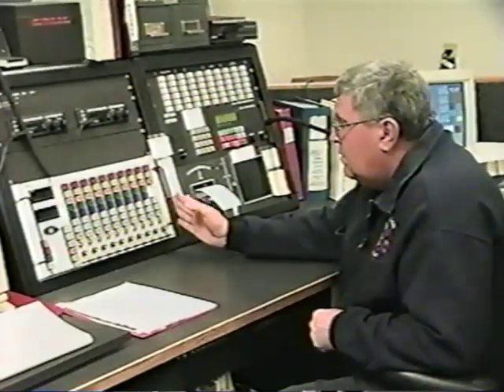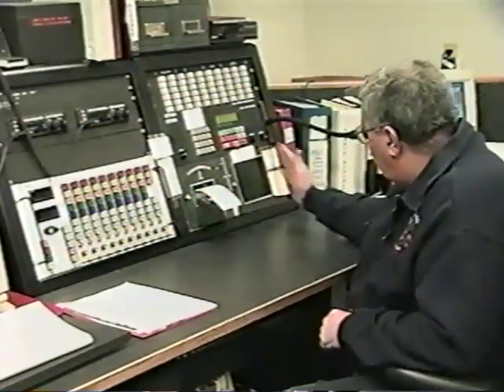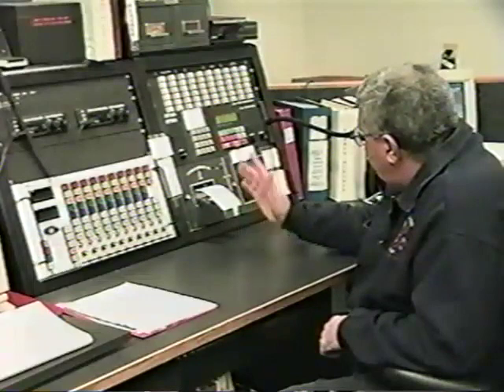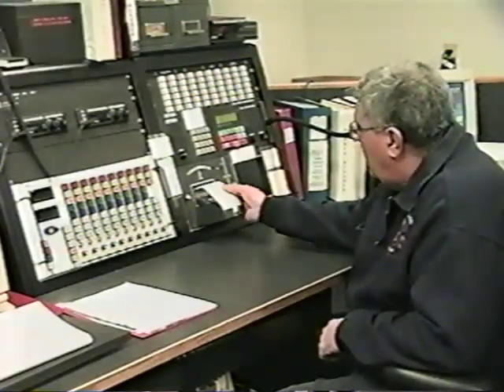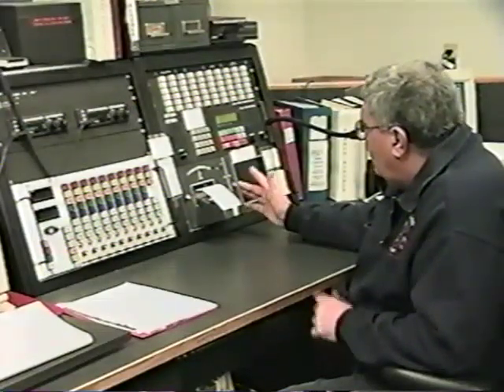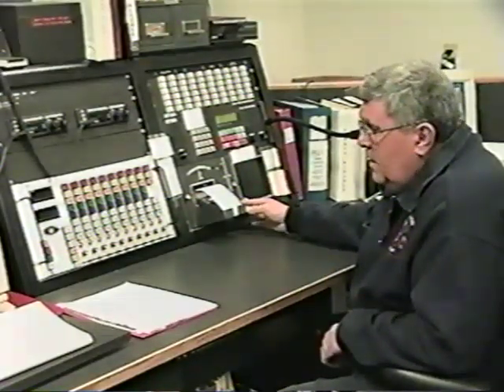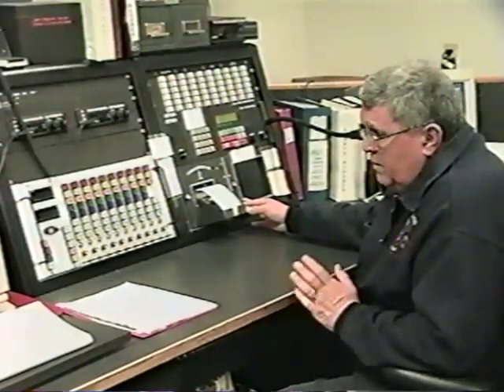So just to go over what I said, the two big brains of the whole place, the Form 4 and the Keltron: everything's going to come through one unit or the other, sometimes both. The information will print right in front of you, numbers, on a hard copy here, and on the screen. It gives you locations. It can even be as sophisticated as to give you individual devices: smoke detectors, pull stations, sprinkler flow valve. So I think we should go out to the low voltage room now, and I'll show you how the circuits actually get in here.